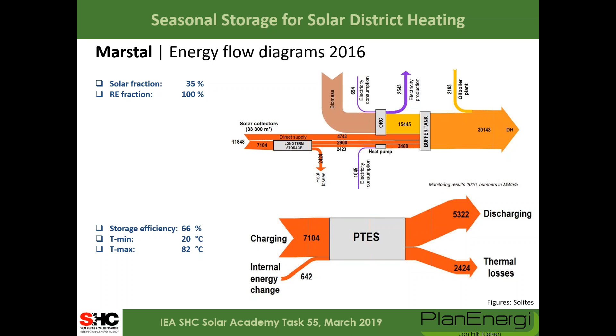We have done some measurements. On this system we have a solar fraction of 35%, and they claim to have a renewable energy fraction of 100% because they fire with biomass. If we look at the energy balance of the store, we see a storage efficiency of 66%, meaning 34% is lost. We have temperatures between 20 and 82 degrees.